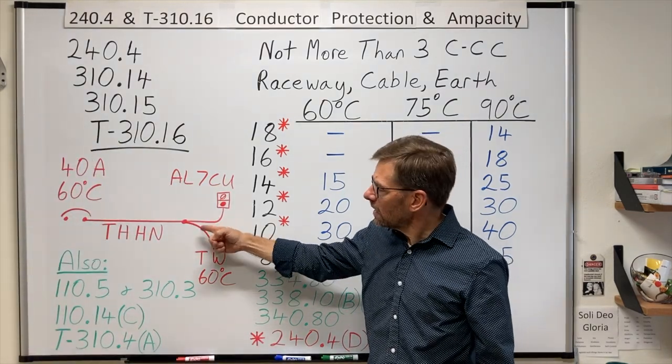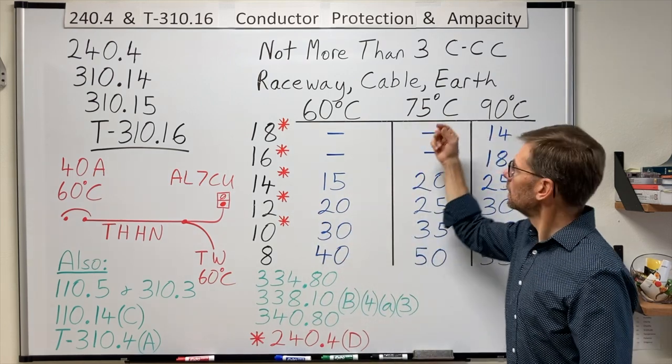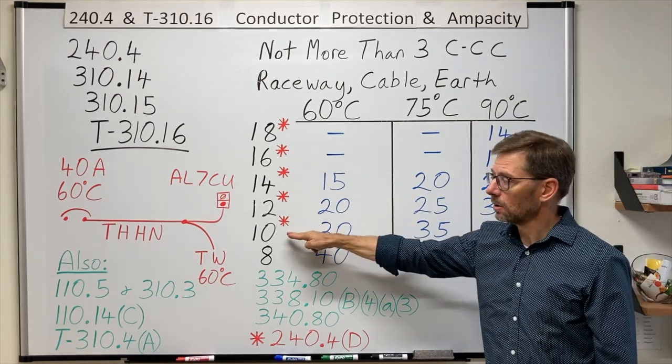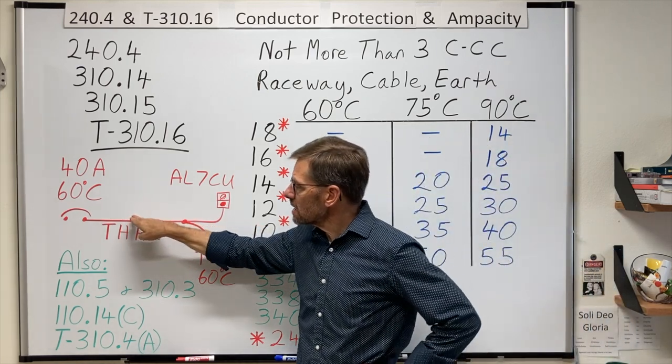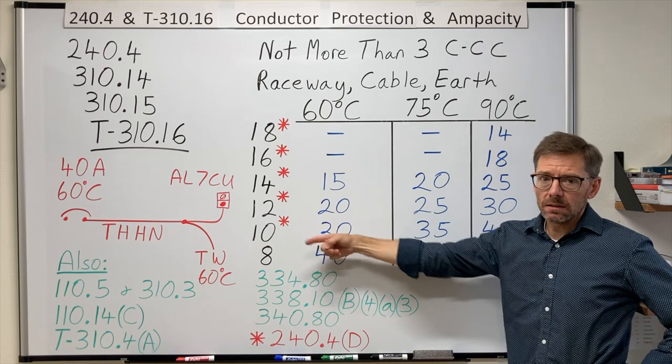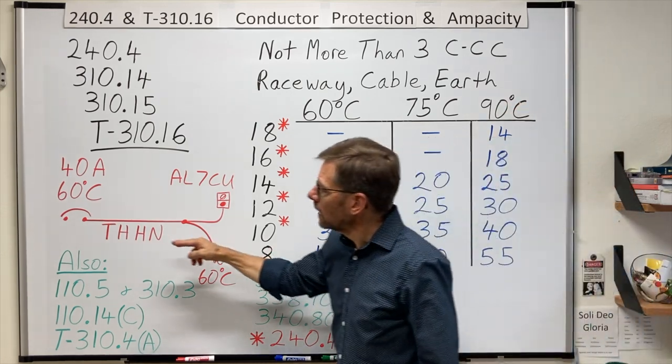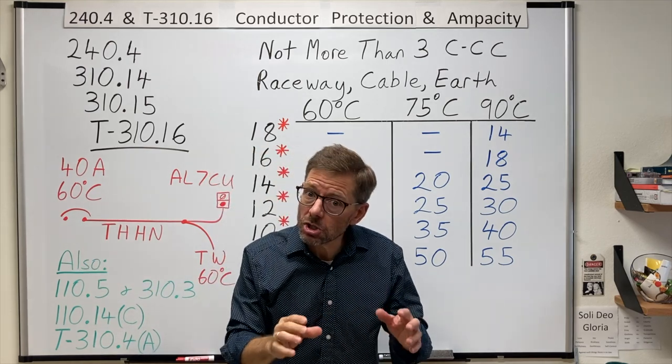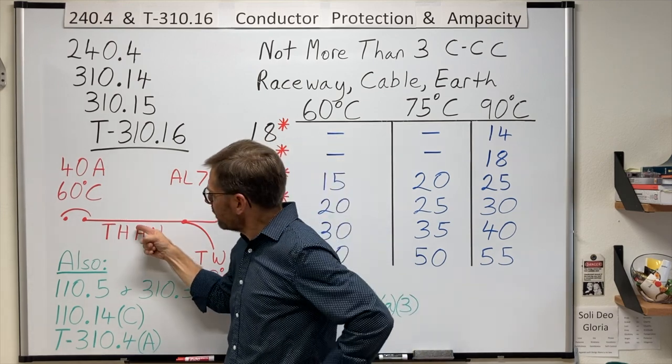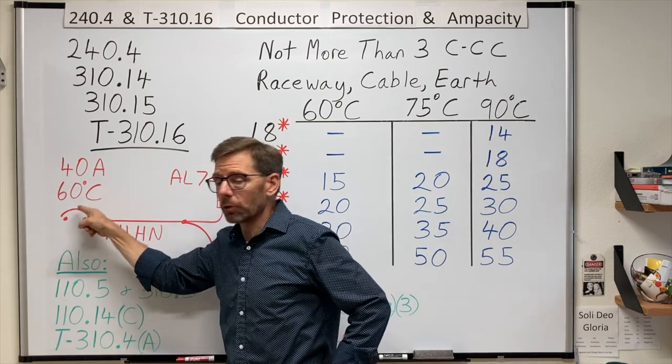You might think in this scenario, with a 40 amp breaker and THHN wire, that I can look at the table, find THHN in the 90 degree column, go down and look for 40 amps, and say a number 10 will be adequate. But let's consider what happens if I put a number 10 in there. If I run 40 amps on a number 10, is that conductor likely to get up close to 90 degrees Celsius? Sure.